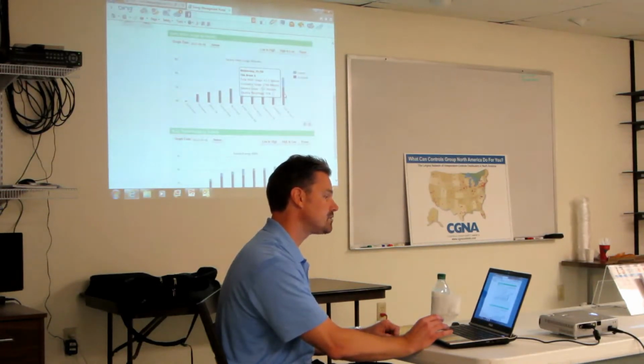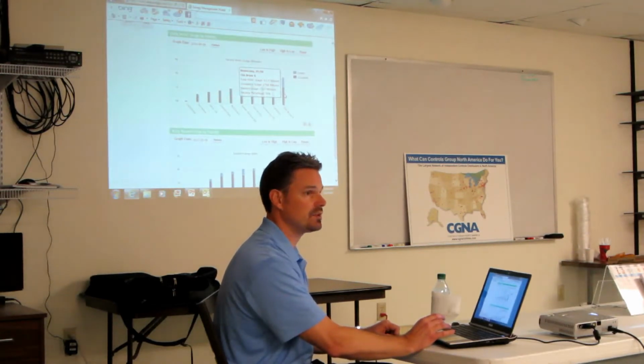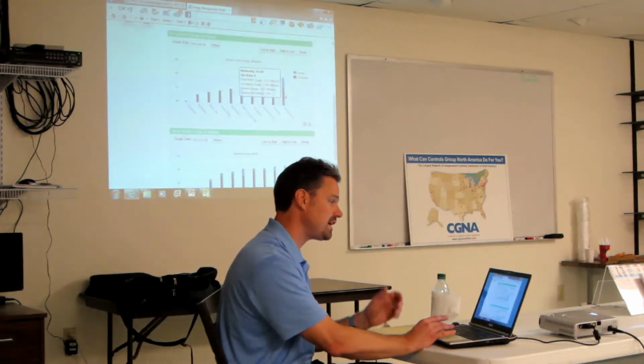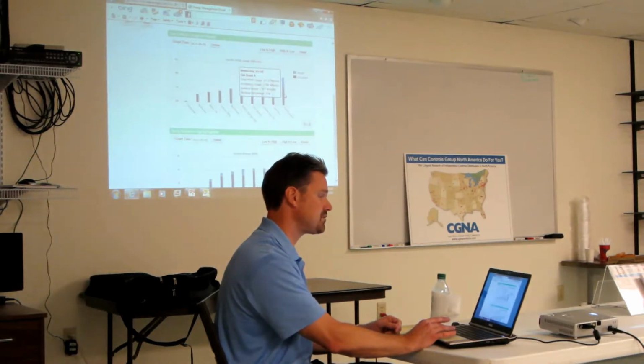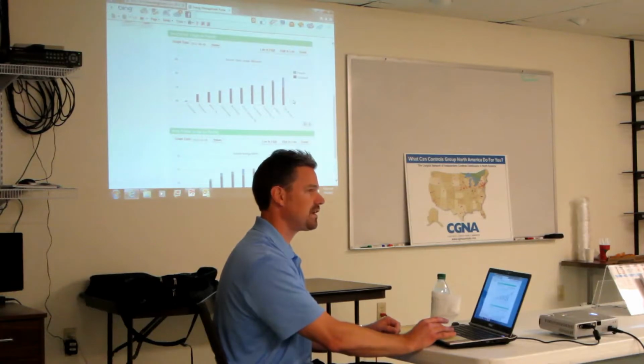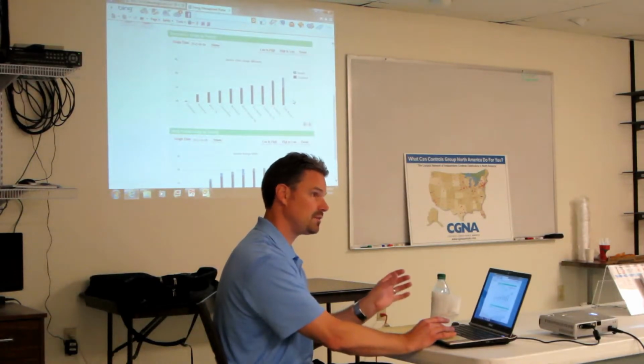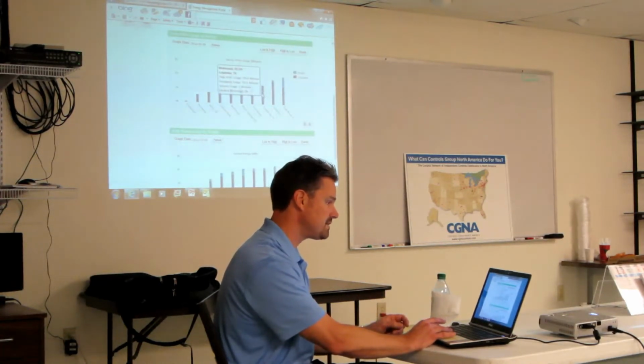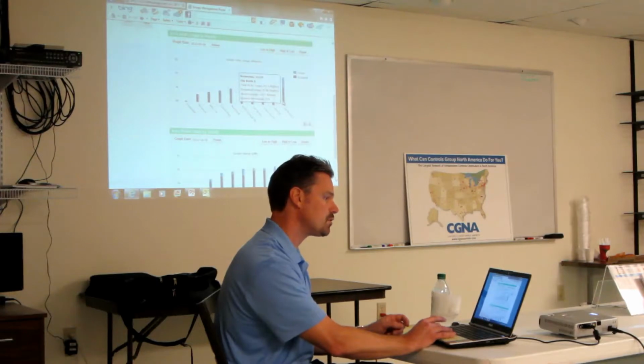Of that, 2786 was during occupancy. But they had vacancy minutes of 1527, so 35%. Now, why is that? If you look just at a glance, you look at all their other ones, they seem to be pretty much either no runtime minutes during vacancy, or very little. Why is this one so much?